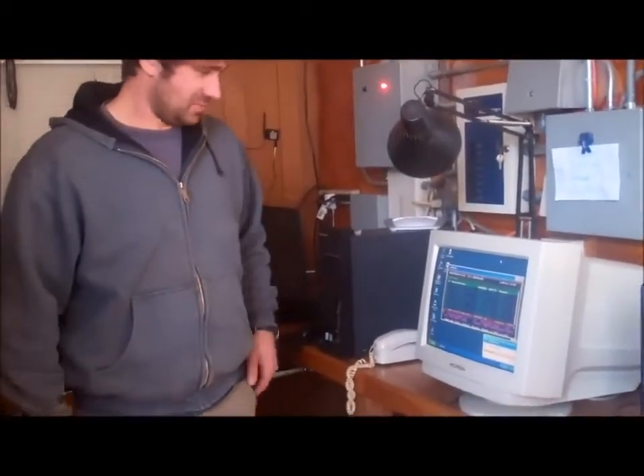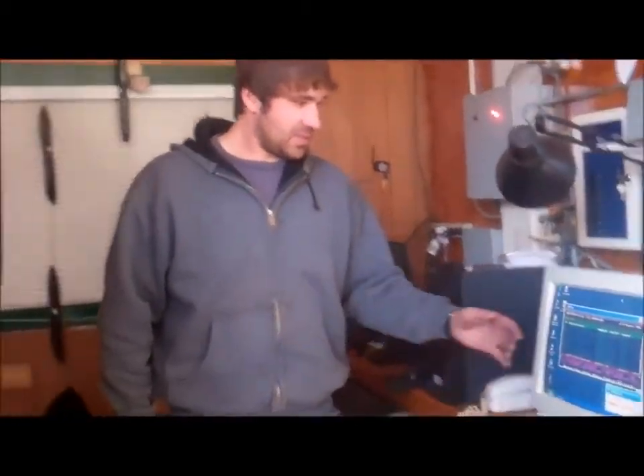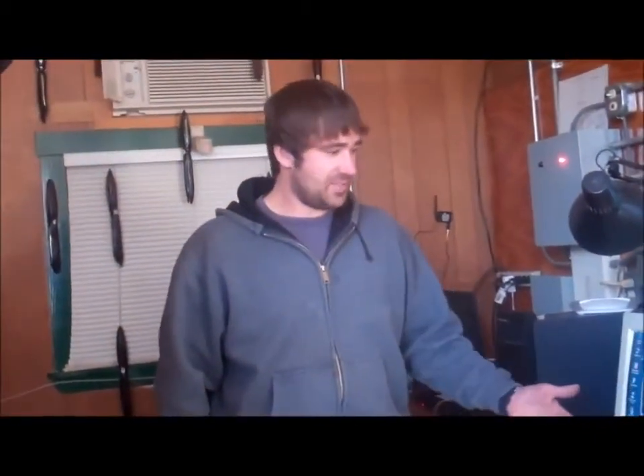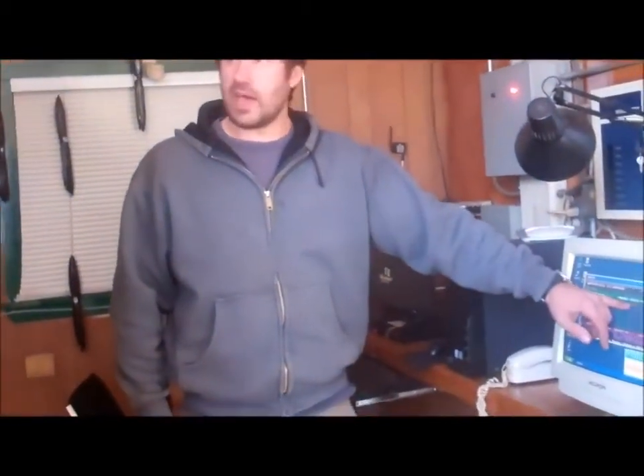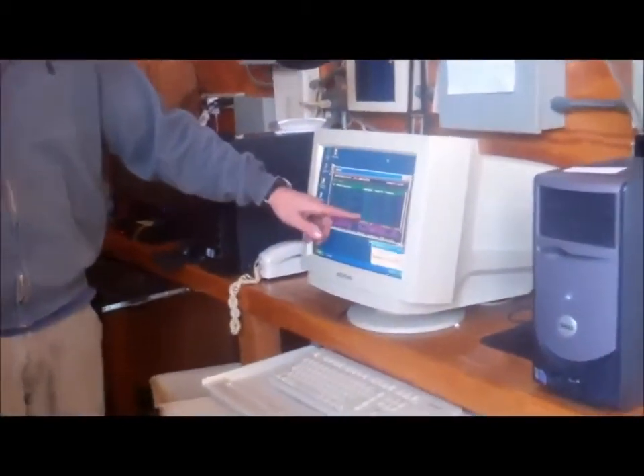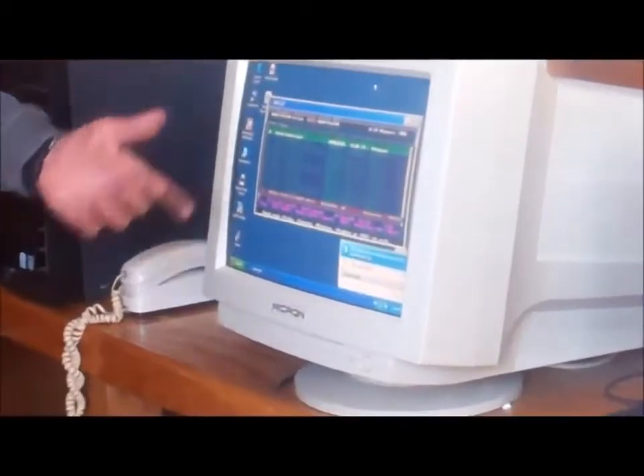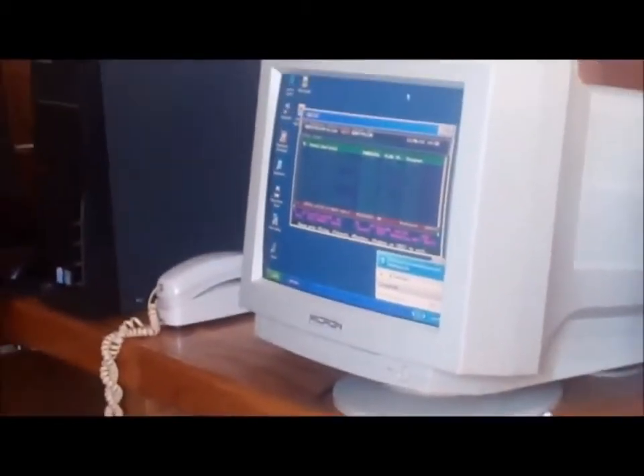So we had to modify the computer and everything to be able to accept it, but it's advanced enough that I've got my pond level down to 1/100 of an inch. So if I can detect changes that, you go up there and you look and you can't see that there's been a change in the pond level, and the computer's picking it up. And I've got the outputs of each of the machines, every bearing temperature, the room temperatures, which is important in the winter so nothing freezes up.